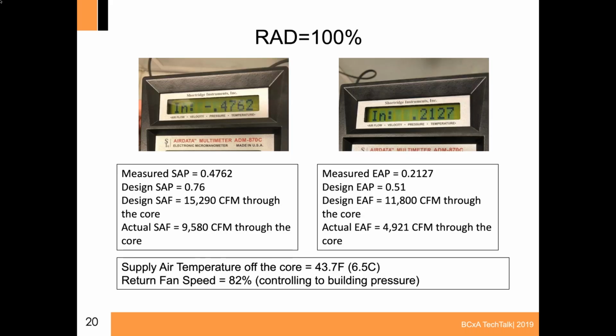So we took pressure readings for the baseline, and you can see that for supply, we had about 0.476 inches water column, and the design was supposed to be 0.76. So instead of the 15,000 or so CFM we should have had, we were only getting just under 9,600. For the exhaust side, similarly, it was low, 0.21 over the design of 0.51, and we were at about 4,900 instead of 11,800. Now, if you recall, I said the minimum amount of flow through the core was 6,200 CFM. Without getting that, we were basically not getting any heat transfer, and that was the reason why our mixed air temperature was so low off the core.